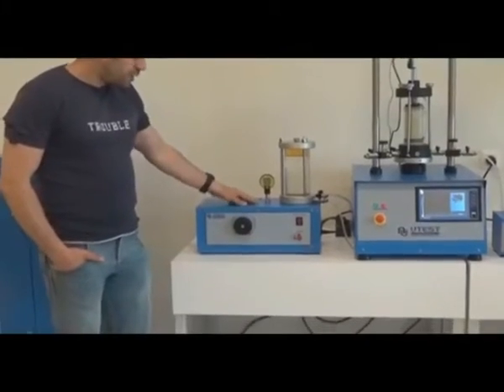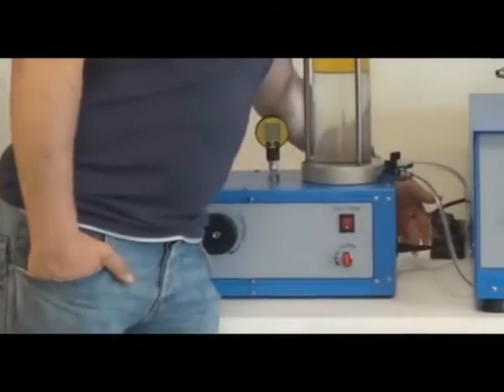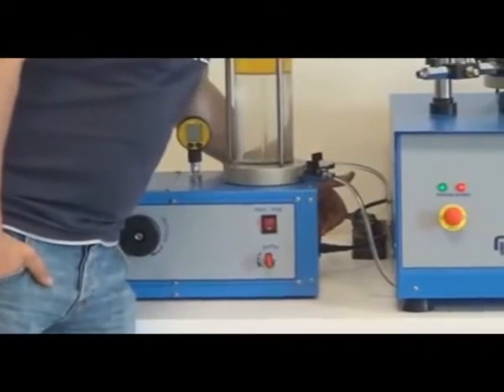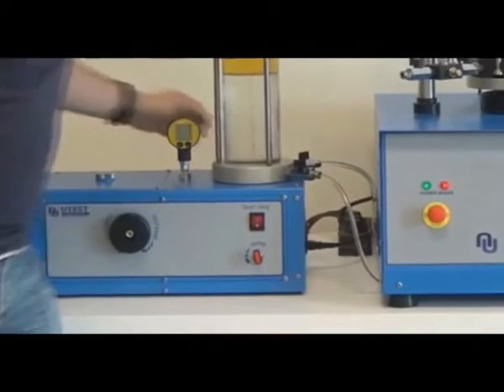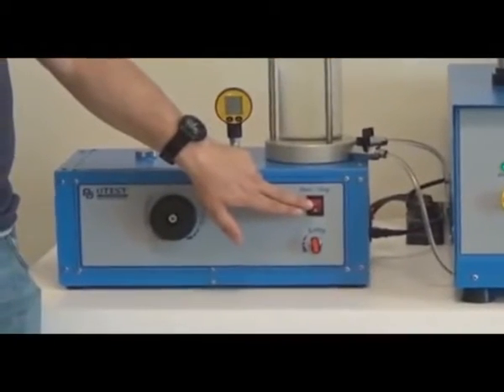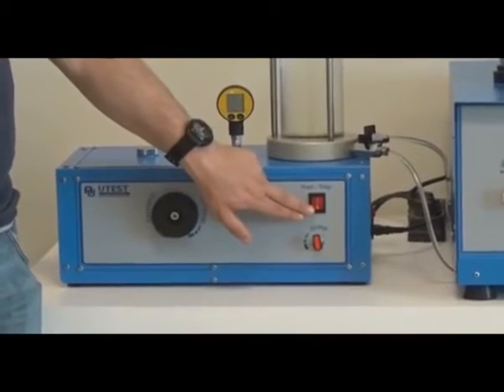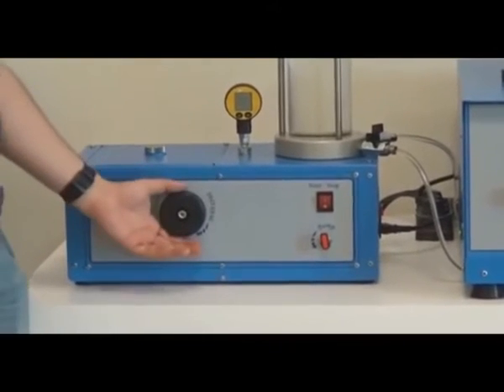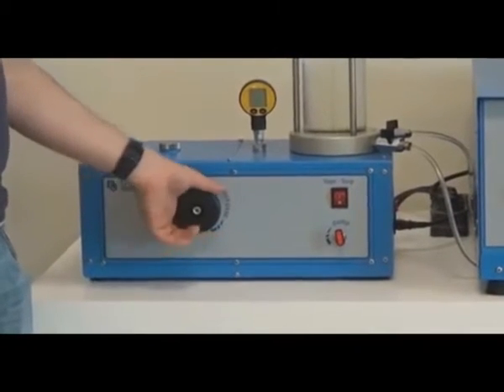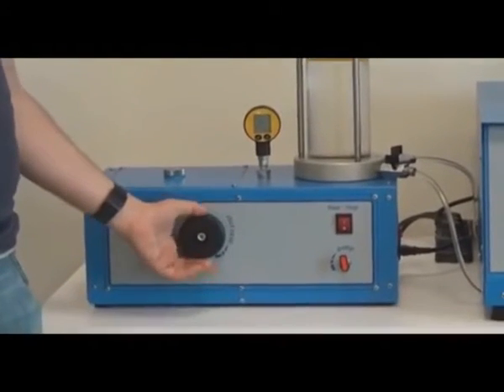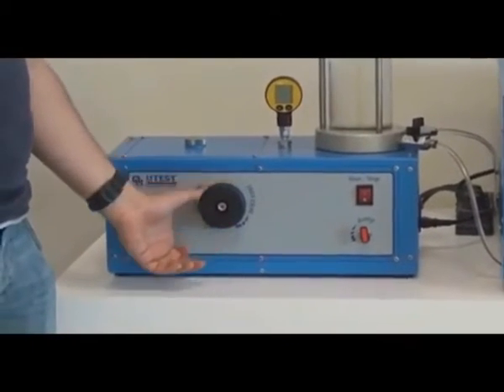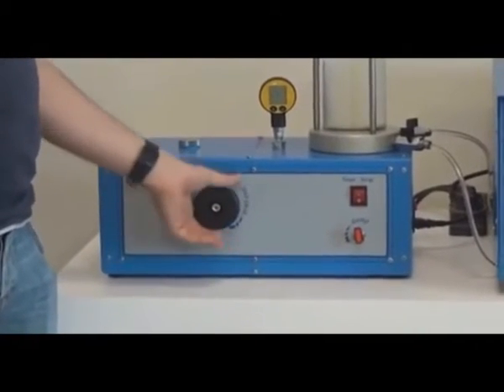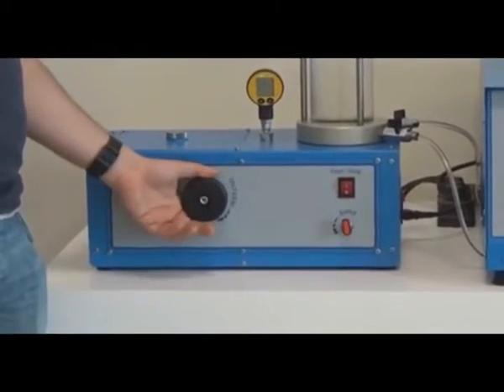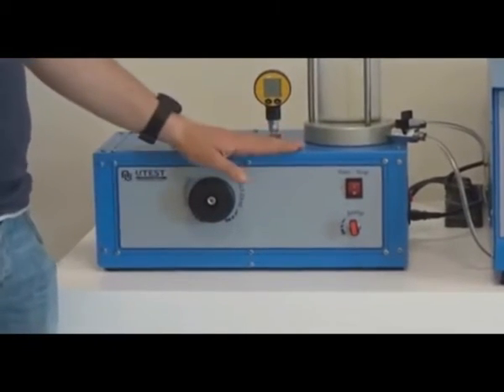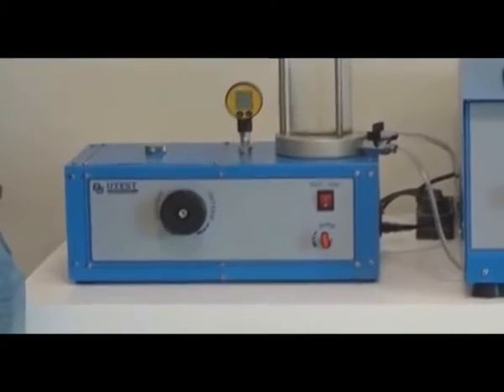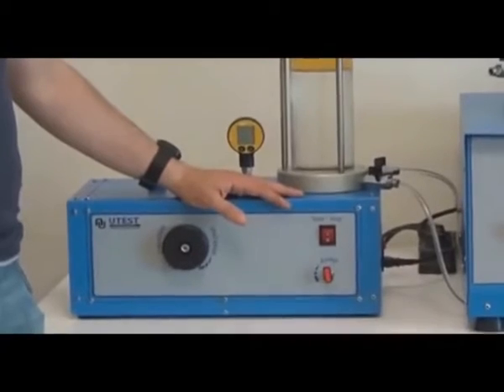The constant pressure unit has a power inlet on the right side and a power on and off button just above the power inlet. We also have a start and stop button which initiates the machine and stops it. We also have a pressure control knob over here. While we are turning it in the clockwise direction, it increases the pressure. While turning it in the counterclockwise direction, the pressure is decreased. This is just to maintain a constant pressure before giving it to the cell or inside of the specimen.